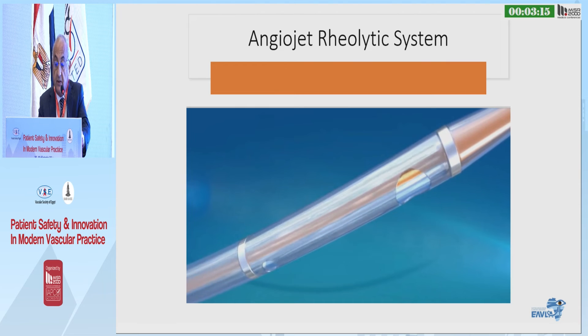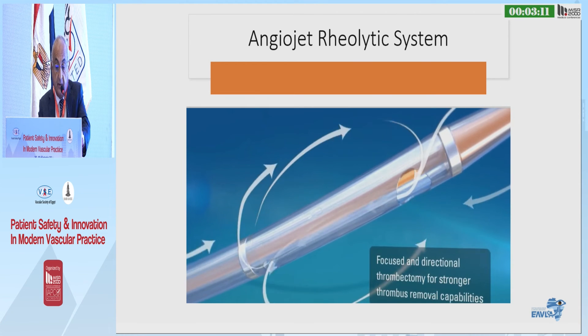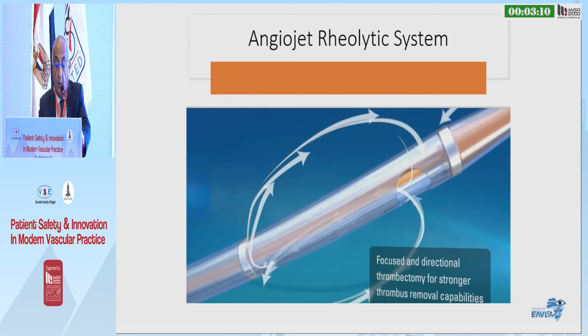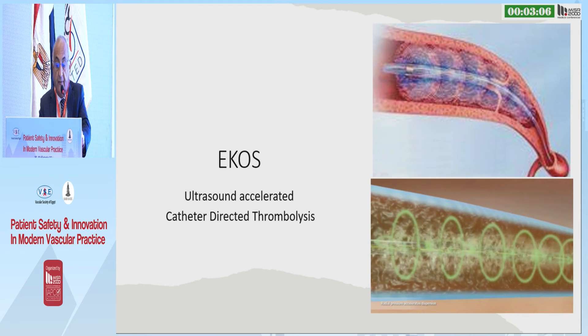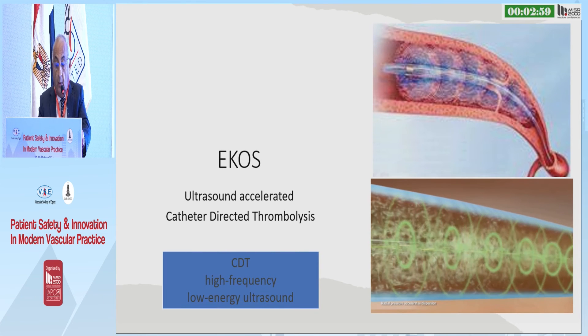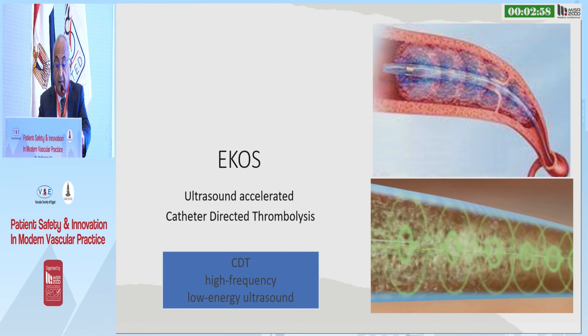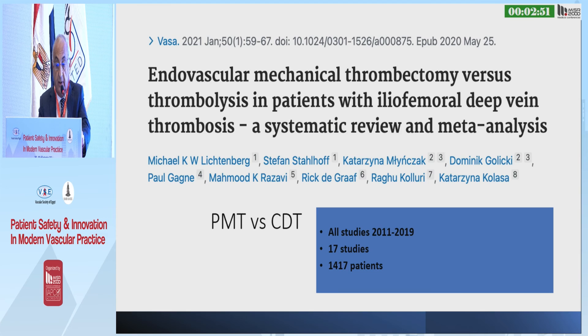The AngioJet rheolytic system injects heparinized saline, producing a vortex current which sucks out the thrombus. And finally, ultrasound-accelerated catheter-directed thrombolysis — the EKOS system — uses a catheter which produces high-frequency, low-energy ultrasound that fragments the fibrin clot, thereby improving the function of the thrombolytic agent.